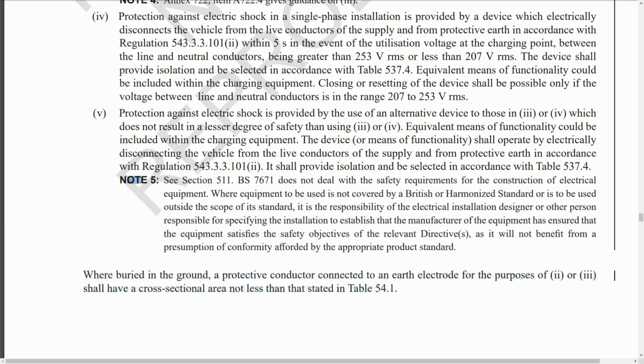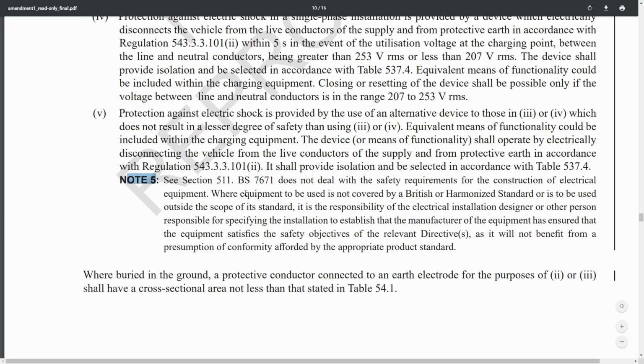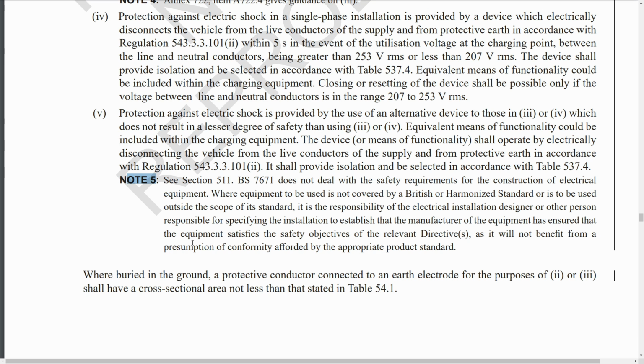And the note 5 here, as it says here, BS7671 does not deal with safety requirements for the construction of electrical equipment. Where equipment to be used is not covered by a British or harmonised standard, or to be used outside the scope, it's the responsibility of the electrical installation designer or other person responsible for specifying the installation to establish that the manufacturer of the equipment has ensured that the equipment satisfies the safety objectives of the relevant directives, as it would not benefit from a presumption of conformity afforded by the appropriate product standard.